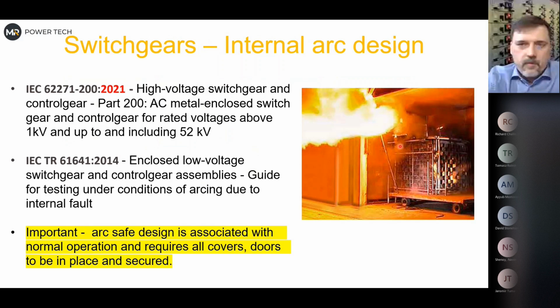So if we talk about the switchgears, and I mentioned the internal arc design, mainly in Europe we will refer to IEC 62271. There was a new release last year, and I will show you a video of what this means. It's easier. The same for the low voltage, so the guide for testing assemblies under arcing.